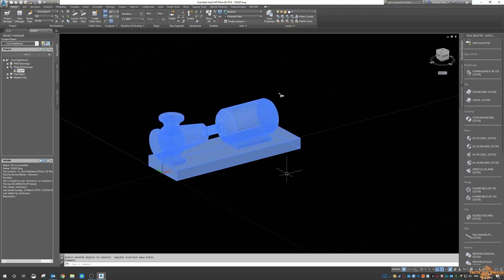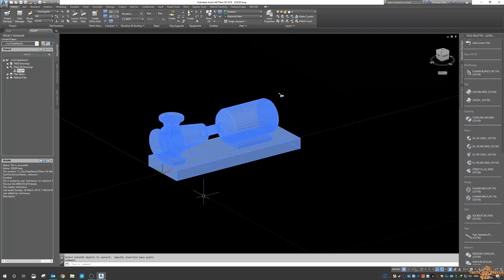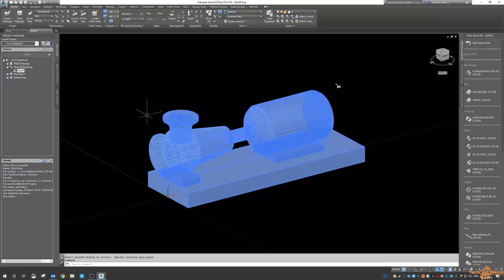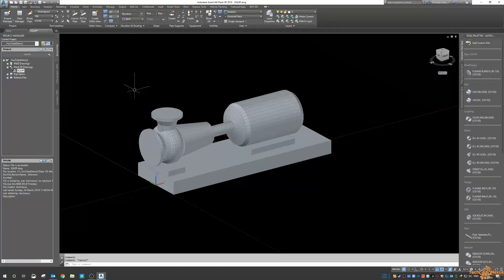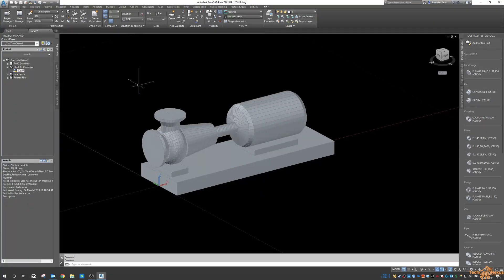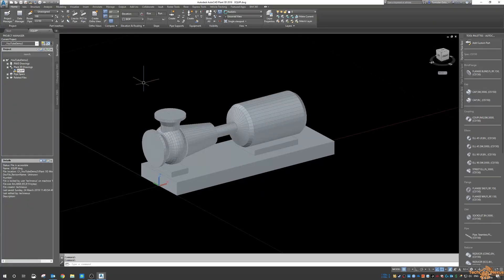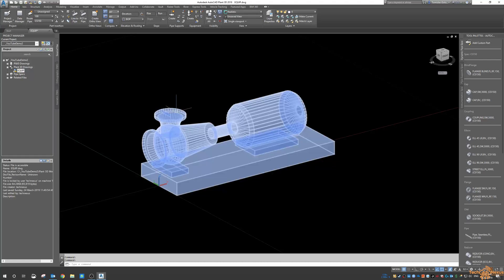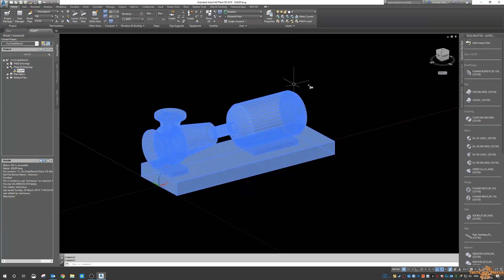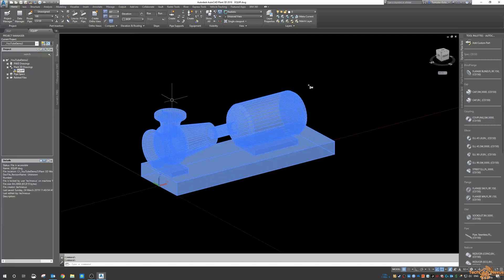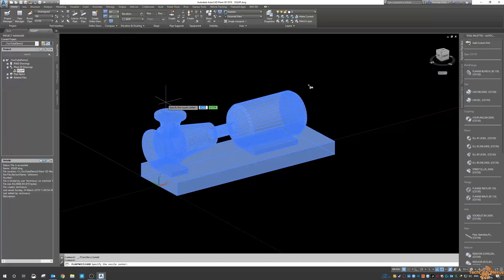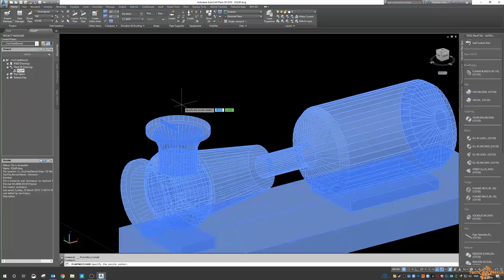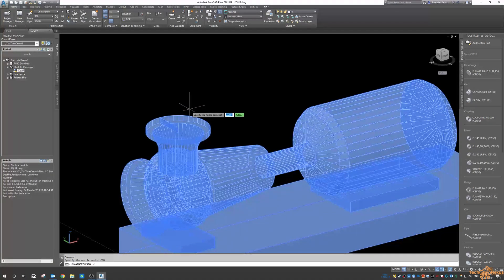Now this is not going to behave like a normal Plant3D pump. You will need to modify the nozzle connections here. So when you convert a piece of AutoCAD block into a piece of equipment, you need to add the nozzles manually because it doesn't have the smarts to dynamically add them through the normal plant channel. So we just click on add nozzle and then I say select the center of this circle here.